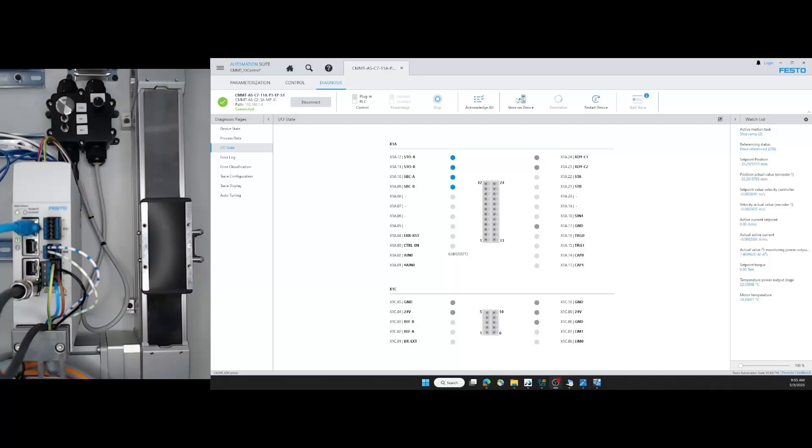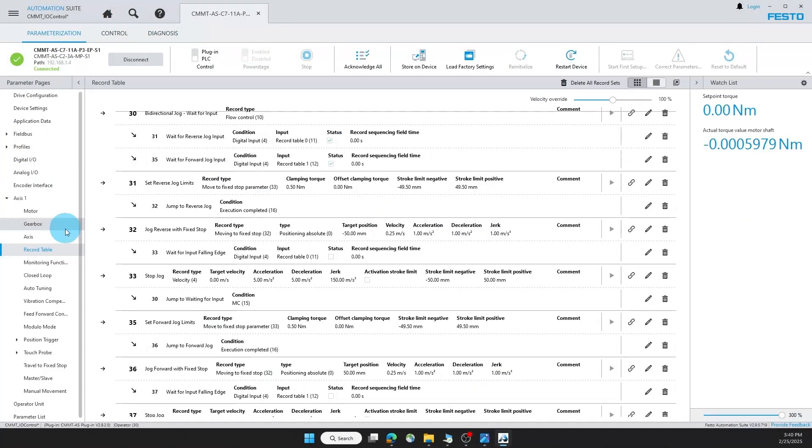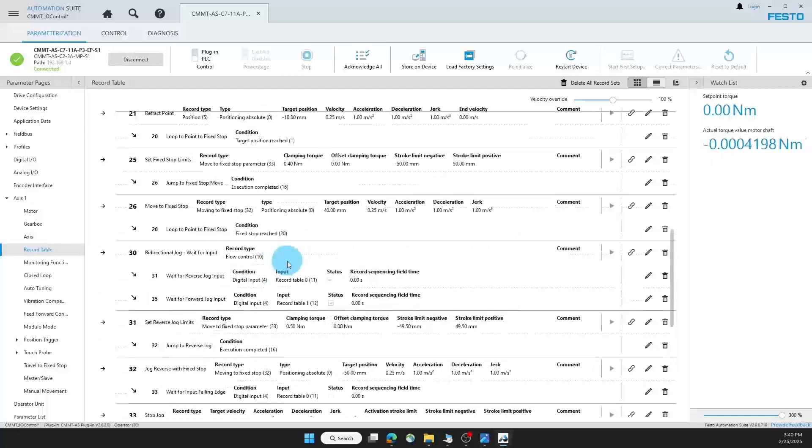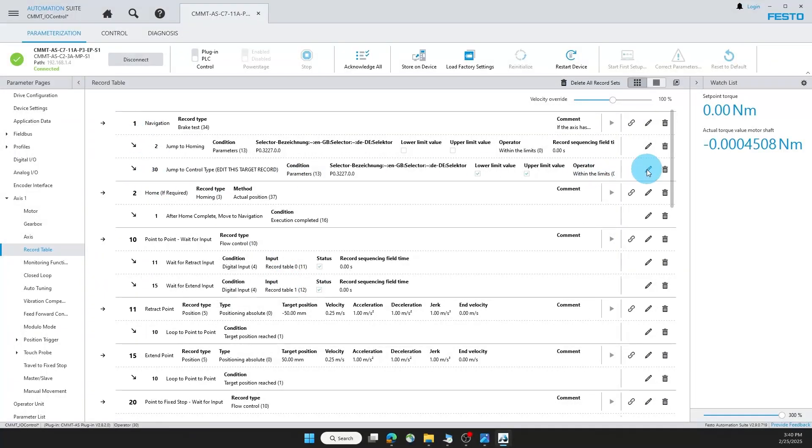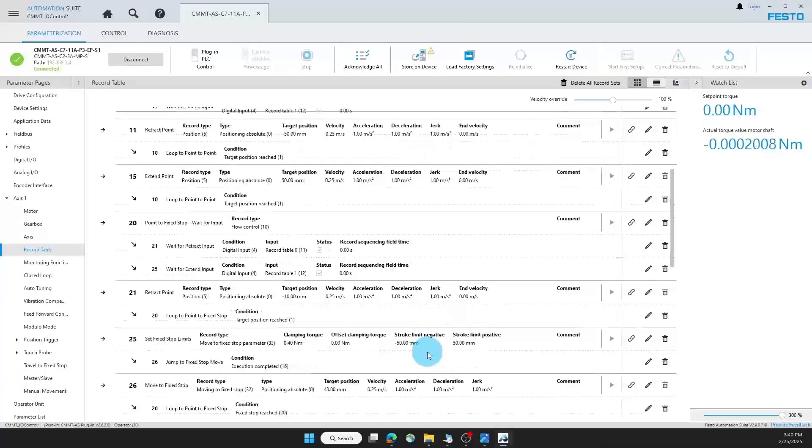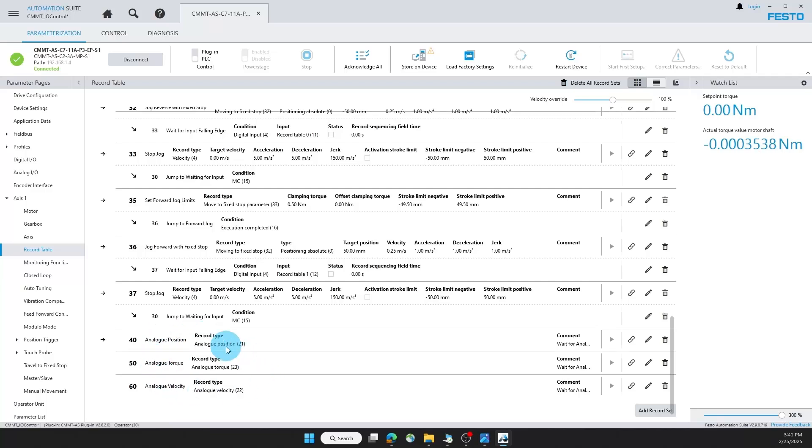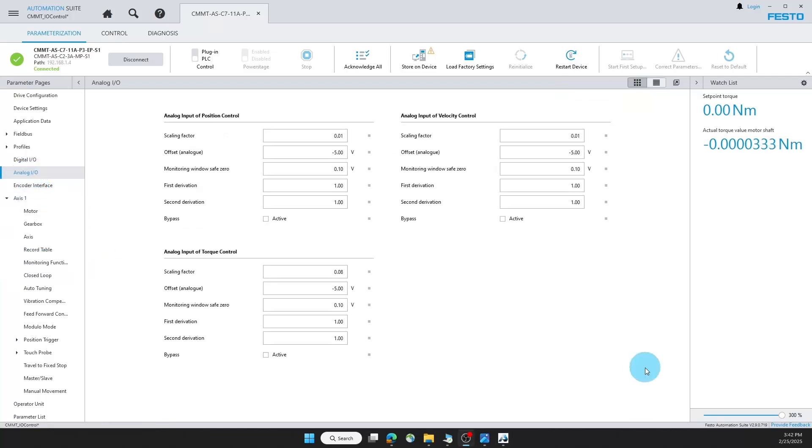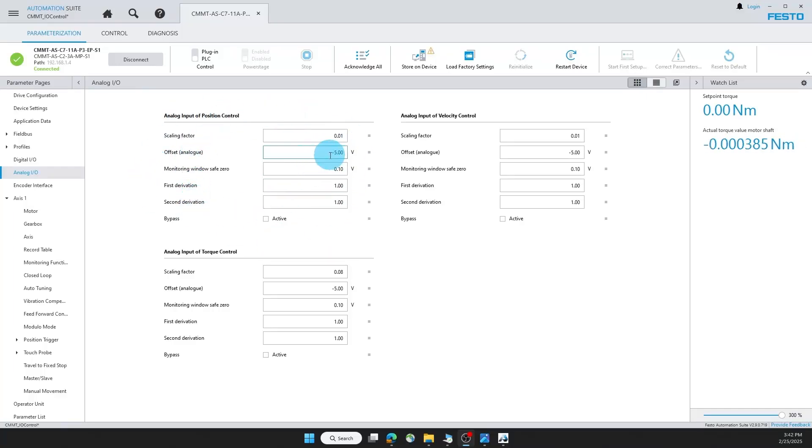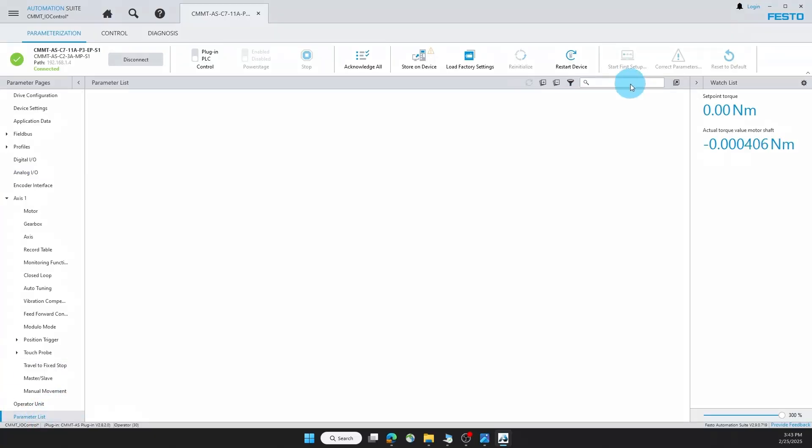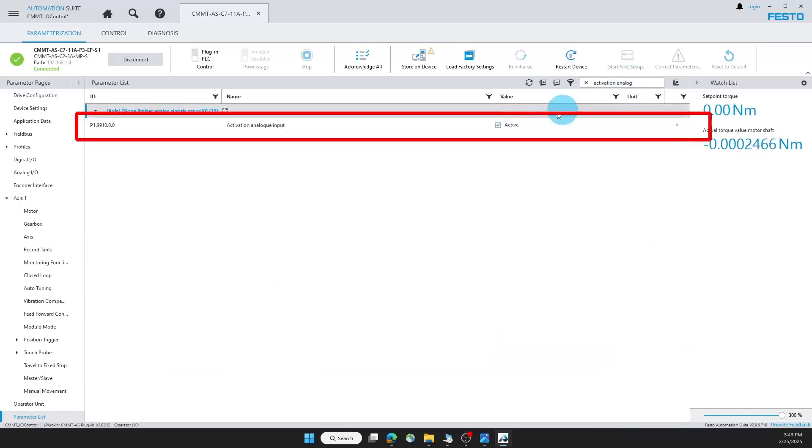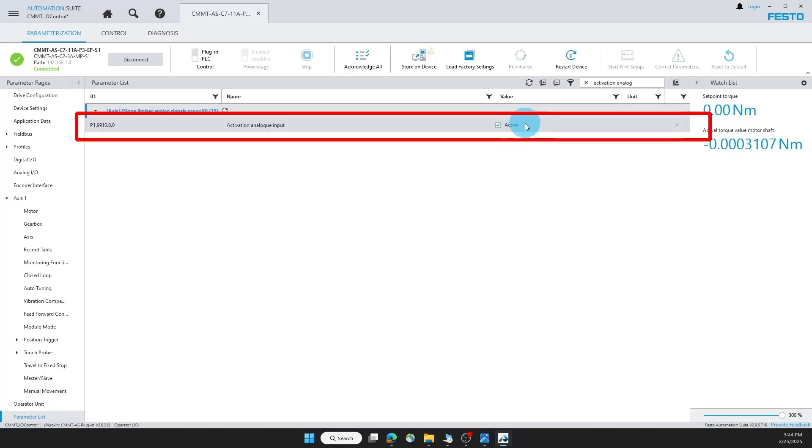Now we can take a look at analog control. If I go back to parameterization in the record table, I can change record one transition to 40. For all the analog control types, there's just one record for each control. But now I can edit how it behaves under analog I.O. In the PowerPoint included with the archive, I'll dive into more on how to set these parameters for application. But in this case, I'm able to set offset voltage, where in my potentiometer circuit I can only get a 0 to 10 volt signal. And by having a 5 volt offset, I can therefore have a minus 5 to positive 5 volt window to work within. I'll also want to make sure if I go into my parameter list and I search activation analog, that this parameter is active. By default it is set inactive to prevent accidental use of the analog input.